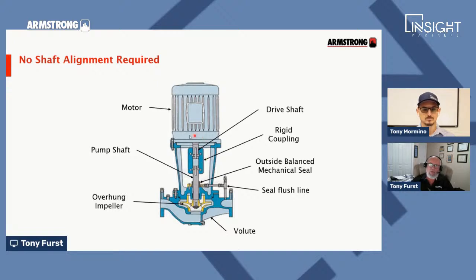So the beauty of this is there's no shaft alignment required. Okay. And I talked about how gravity helps. Well, because gravity is pulling down on this in a straight line, there's no overhung loads. There's nothing cantilevered out the end of the shaft. Now I eliminate a lot of that vibration. That's why these things have such minimal vibration to them.